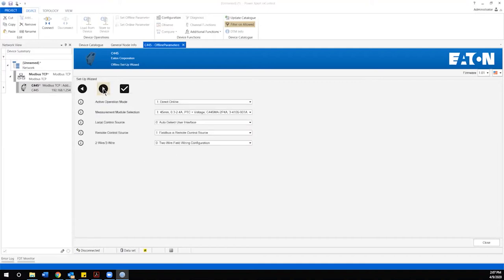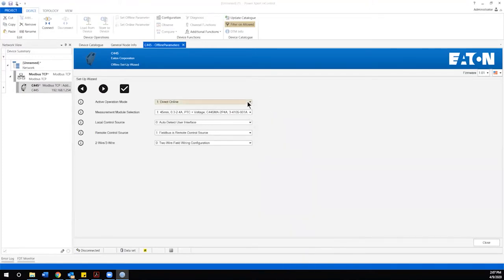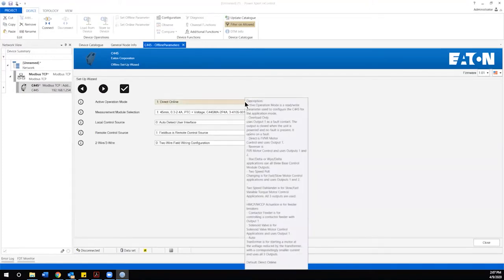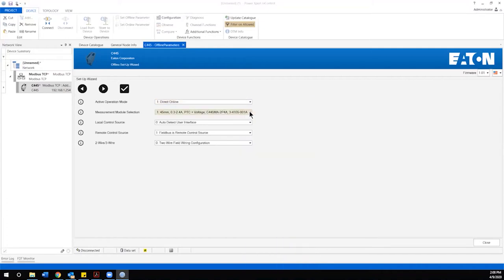Clicking on next takes us into the basic operational controls and first thing we're going to set is what type of operation the C445 is going to be used in. What I really like about this software app is it has the ability to by hovering over any of the input parameters to give some pretty good descriptions of the options that are available. We're going to set this C445 up for direct online operation which would allow us to have remote control capability of the starter through the C445 as well as all the advanced monitoring and protection functions that are associated with it.